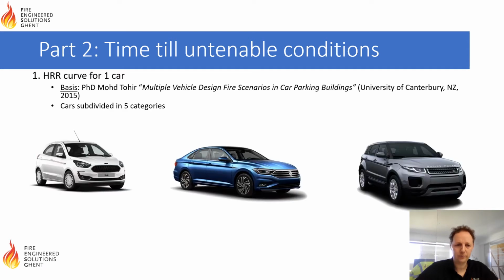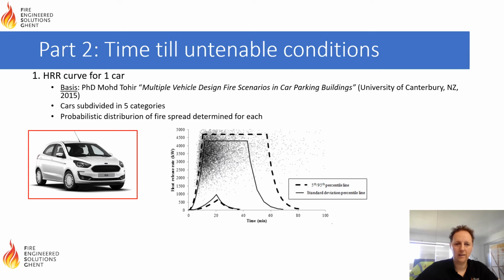Basically he subdivided cars in 5 categories, from smaller cars to larger SUVs, and he looked at the probabilistic distribution of how the fire could evolve. So you have the 5 percentile and the 95 percentile here for a smaller car. If you burn the smaller car 100 times, for 5 fires the heat release rate won't be larger than 500 kilowatt, and in 95 of the 100 fires it won't be larger than 4.5 megawatt. And the same for larger vehicles. The higher the mass, the higher the total fire load, and also the higher the heat release rate, as it's mainly driven by size of the windows, as we will see in a minute.